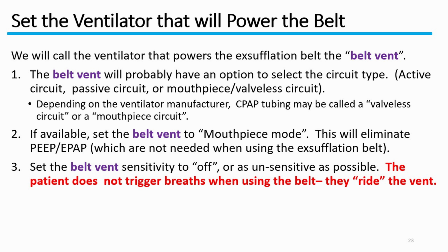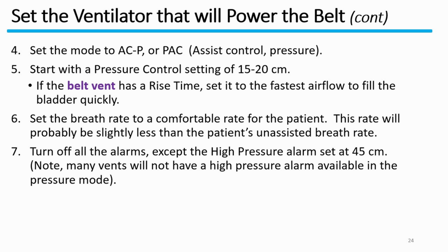If available, set the belt vent to mouthpiece mode. This will eliminate PEEP or EPAP, which are not needed when using the exsufflation belt. Set the belt vent sensitivity to off or as unsensitive as possible. The patient does not trigger breaths when using the belt. They ride the vent. Set the mode to assist control pressure, or PAC. Start with a pressure control setting of 15 to 20 centimeters.